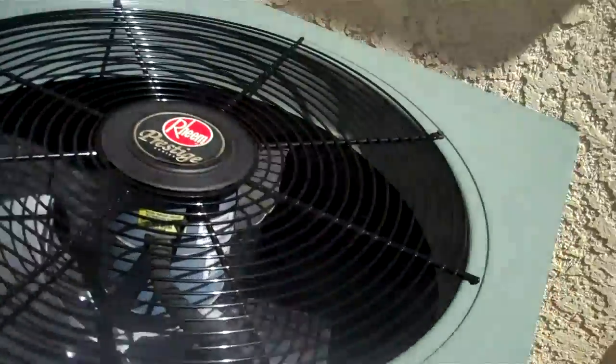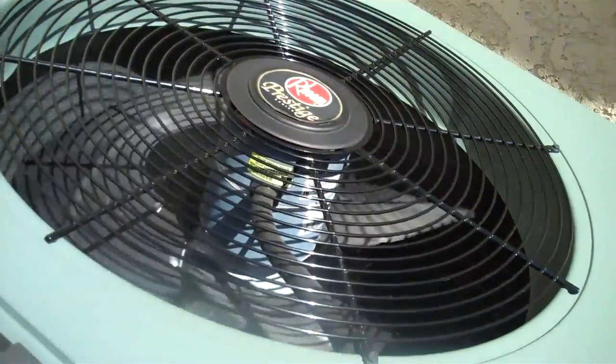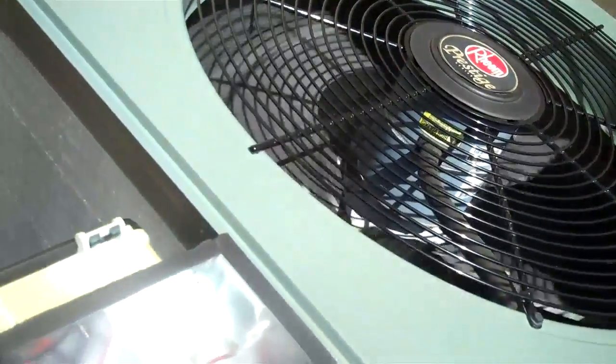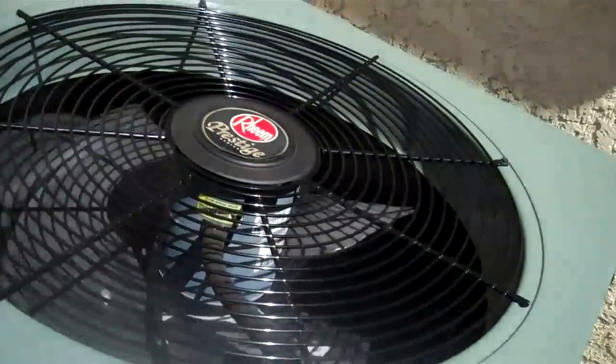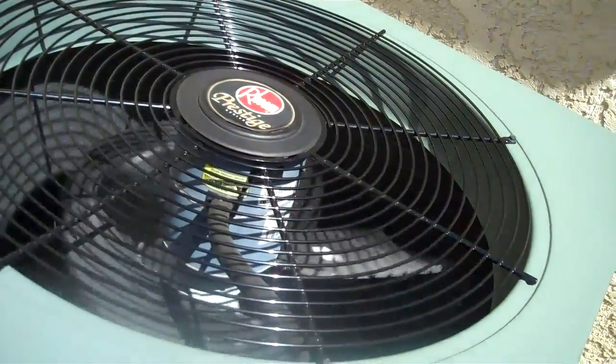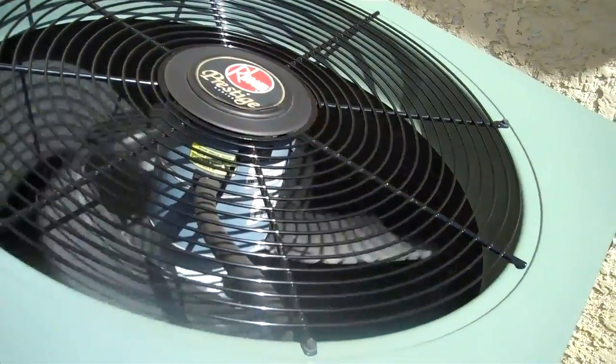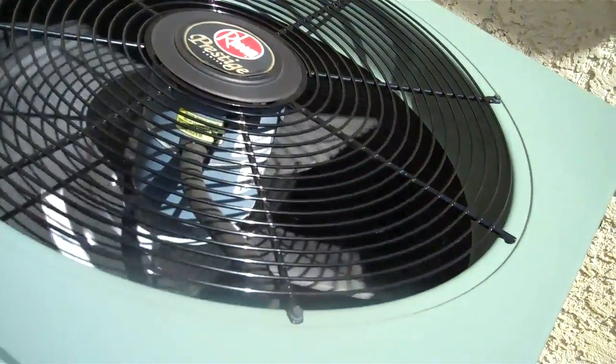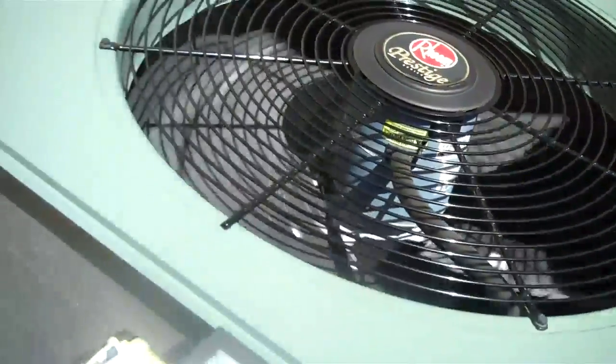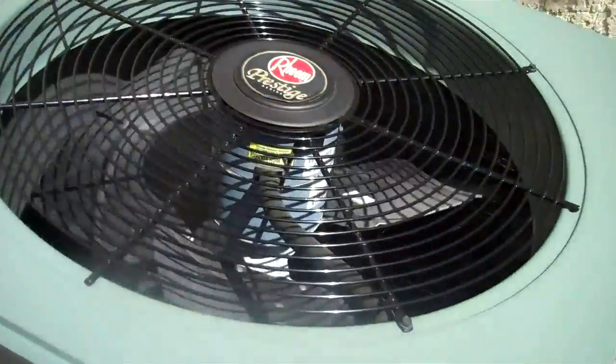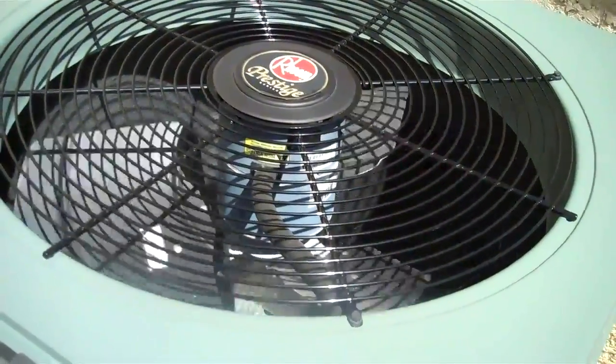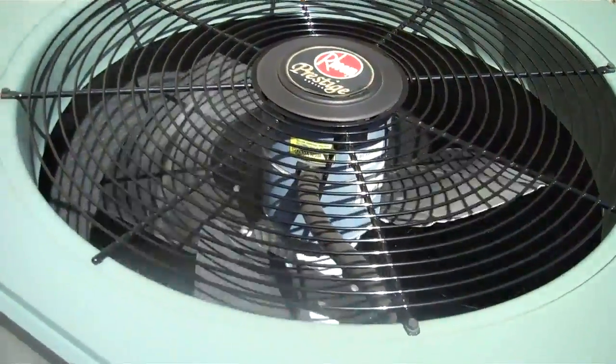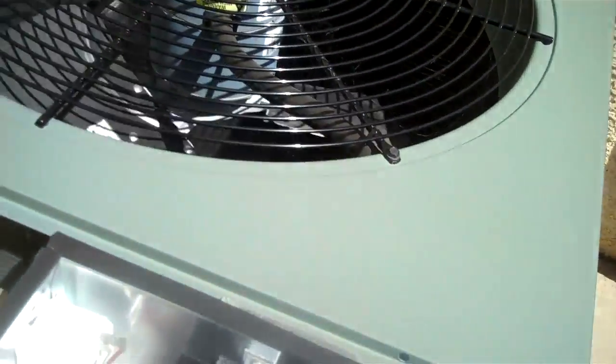Okay, I just bypassed the delay, so here's a call for cooling, this is what it's like when it starts up, so compressor first, then it connects the fan motor, so the AC is running, and then this will be a shutdown. Compressor shuts off first, then the fan shuts off. Basically that's how it just runs all day long, unless you pull up on high speed, then it's going to kick the solenoid up.